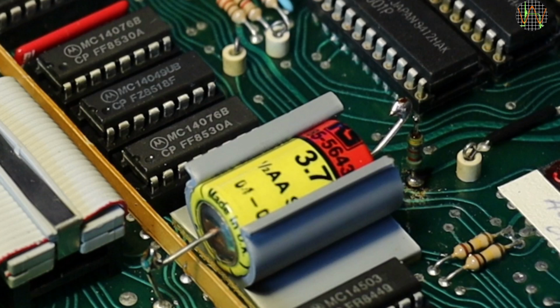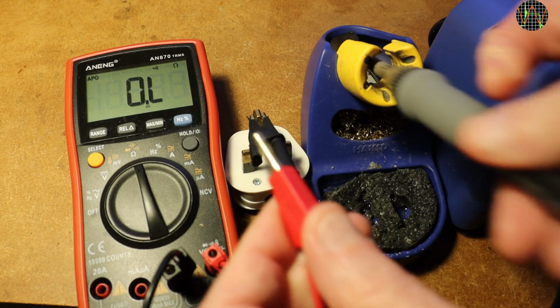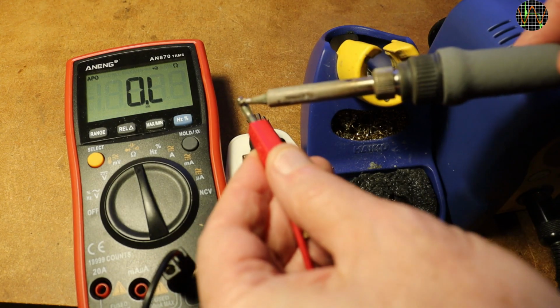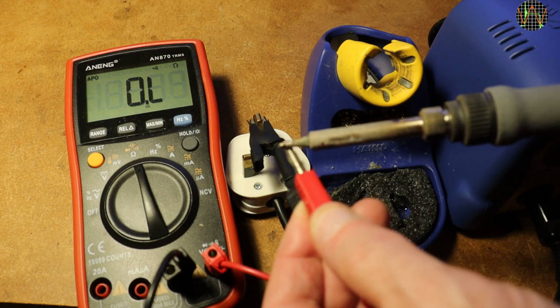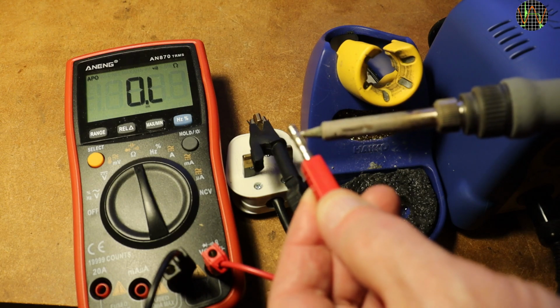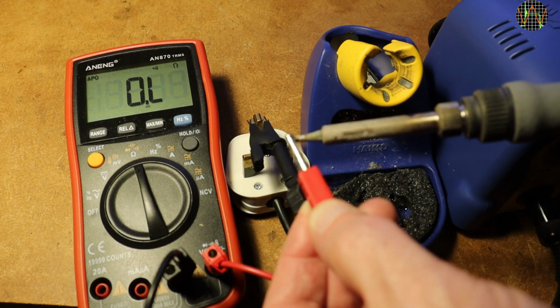Normally you should never solder something while the power is on, but there is not much choice here. The 1065A has to stay powered on to allow me to remove the battery, or I lose the calibration data. Using a normal mains-powered soldering iron is a problem here. The tip of a mains-powered soldering iron is connected to ground for safety.